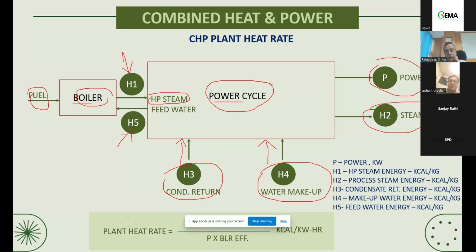Basically, plant heat rate is the indicator of the efficiency of the plant. If you invert the plant heat rate, that means 860 divided by the plant heat rate, you will find the efficiency of the plant. And the plant heat rate is in kilocalorie per kilowatt hour. That means to generate 1 kilowatt hour of power, you require so much heat. And if you divide this plant heat rate in kilocalorie per kilowatt hour by the GCV of the coal or the fuel, you will find the fuel consumption. So that is how one should start evaluating the plant efficiency, which is very important for the capex calculation and creating the capex model for your cogeneration plant and the overall ethanol plant as well.